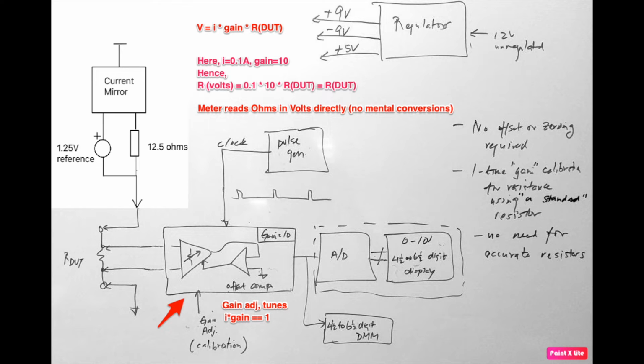The other advantage of this technique is basically you don't worry about any inaccuracy in the 100 milliamp or the reference current. It may be anything, and you can set it to any value you want, maybe 50 milliamps, whatever is convenient. And even the gain resistors in the instrumentation amplifier, where there are several of those, you don't have to worry about those. They can be mismatched as long as they don't vary over time, or due to temperature drift in any way. And so therefore you can use one gain calibration given a known resistor or a standard accurate resistor, and you should have an accurate reading from this instrument.